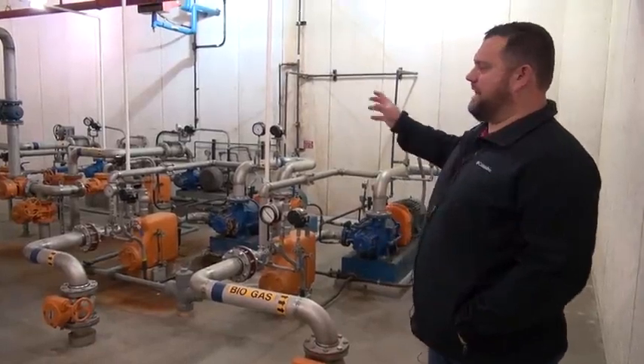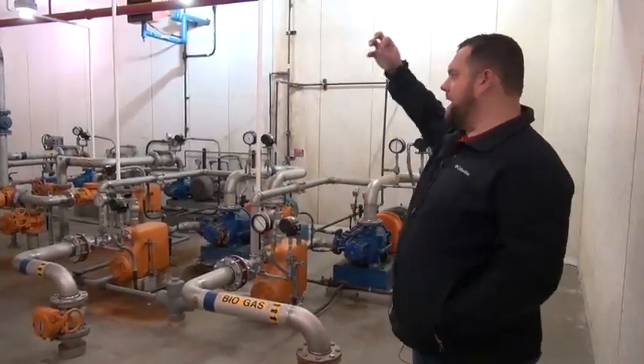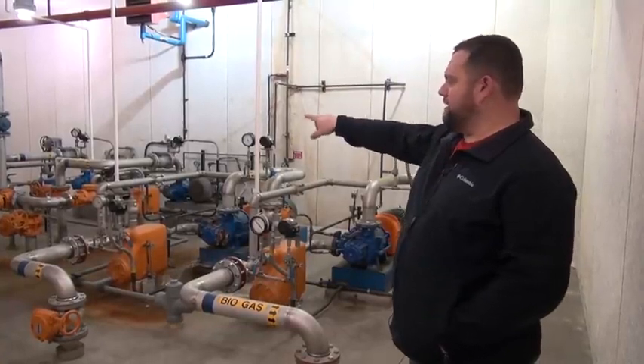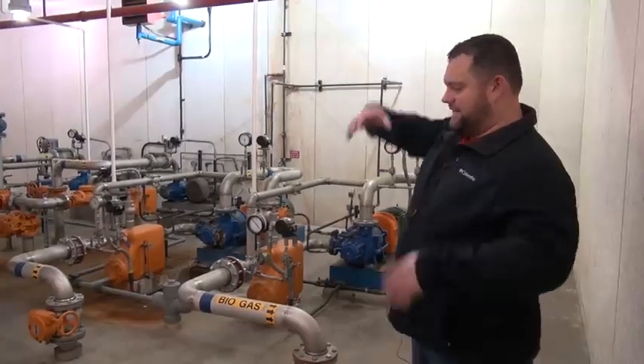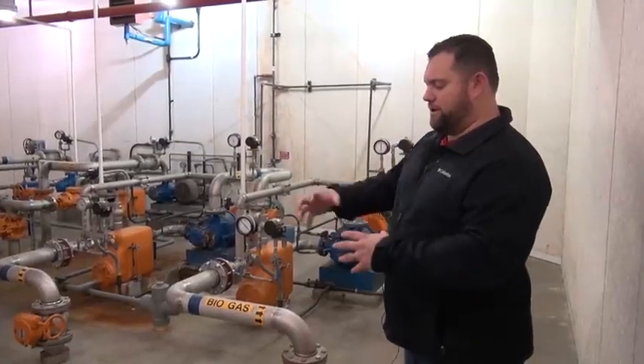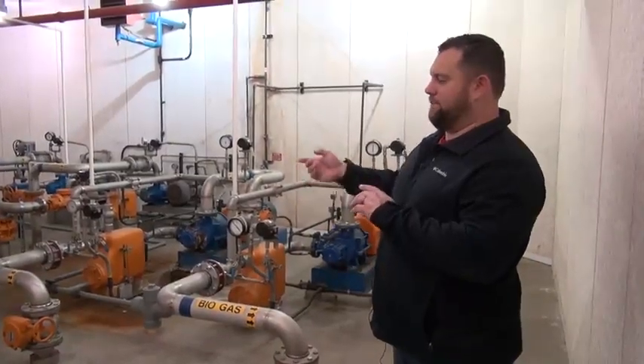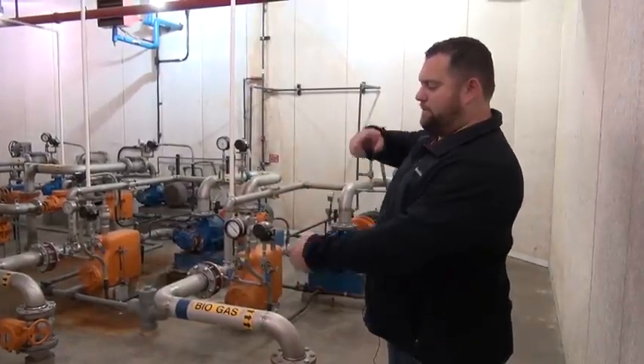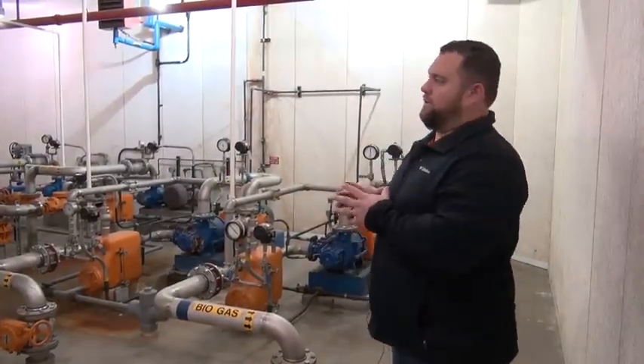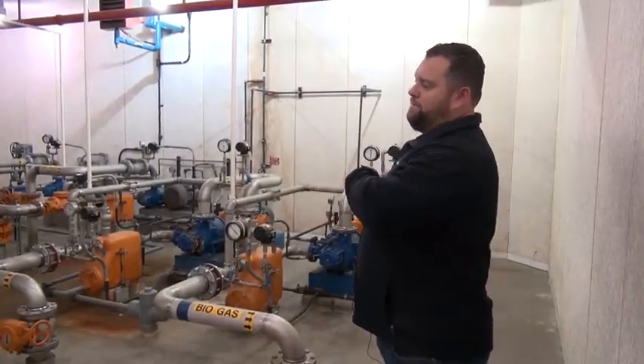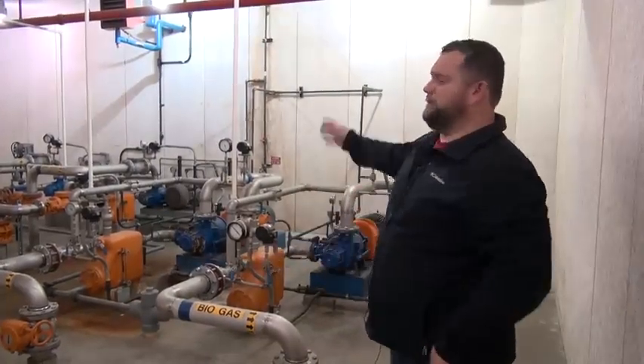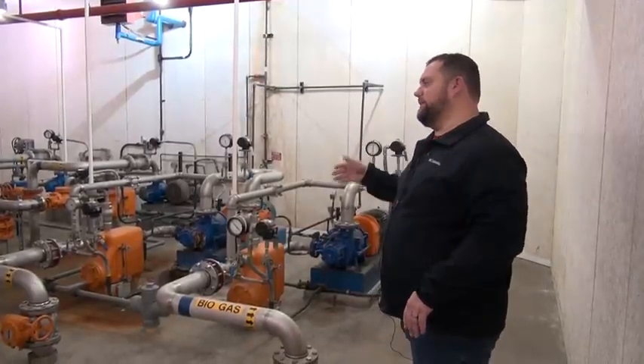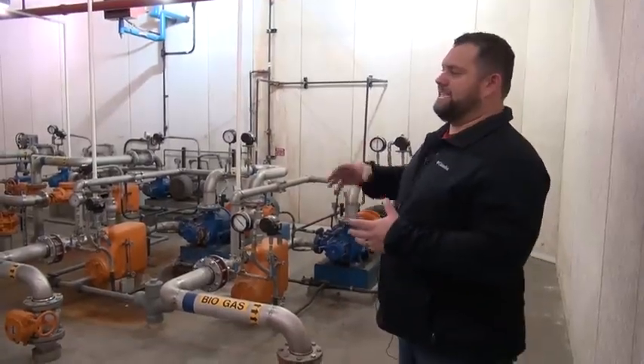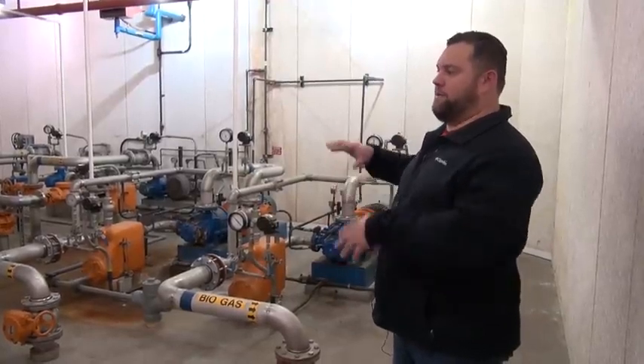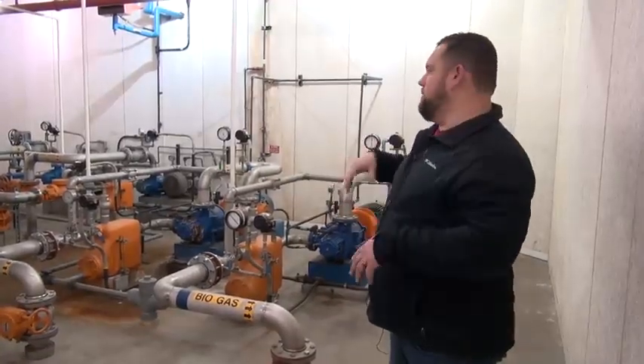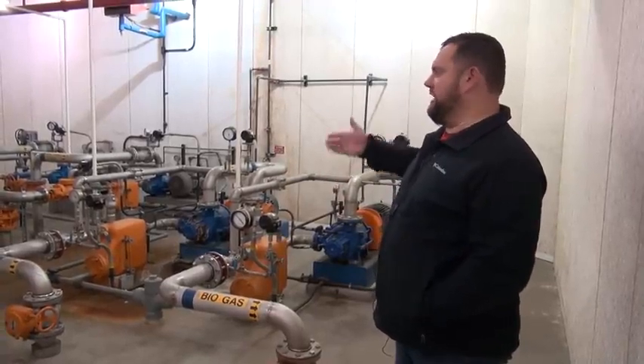We take the methane gas being produced, suck it out of the top, bring it into gas compressors, and send it back into the tank through what's called a cannon, a huge barrel in the middle with holes in it. The compressed methane makes big long bubbles that tumble and mix the tank. So we're using the gas that's produced to burn, to fuel our boilers, and also to mix the tank, a pretty sustainable approach. Some tanks use mechanical mixers with moving parts, or extra pumps with nozzles; we're using gas to turn over our digesters.